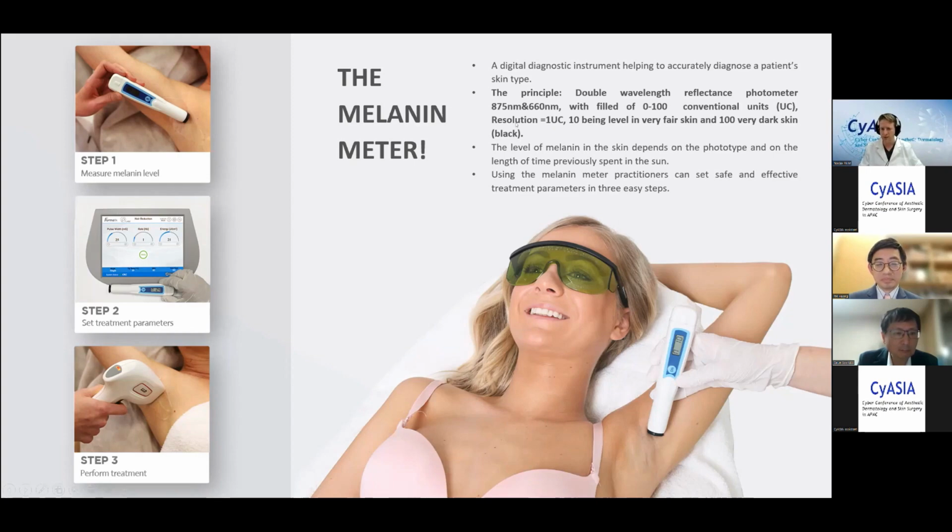So this device measures the melanin at 875 and 660 nanometers. It gives you a scale from 0 to 100. But why is it important? Maybe it's not the doctor doing the treatment, but a nurse, a dermal practitioner, or a cosmetician. So she can measure the melanin content in the skin in different areas, put the parameters in the device, and it will give her much more safety margins.